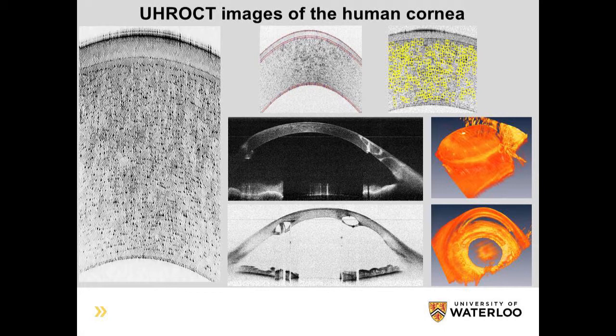The same device, with a different imaging probe, can image the front part of the eye — the cornea — the transparent tissue in front of your pupil. This is a higher-resolution image obtained with approximately 2-micron resolution in the vertical direction in biological tissue. The cornea is about half a millimeter thick and has five distinct layers; the thinnest is about 3 to 4 microns — the size of a nucleus — and with these images we can recognize that layer and see reflections from individual cells.